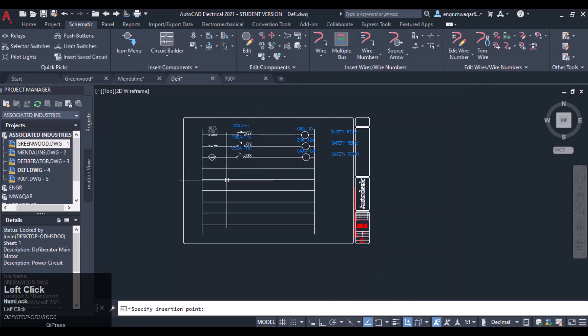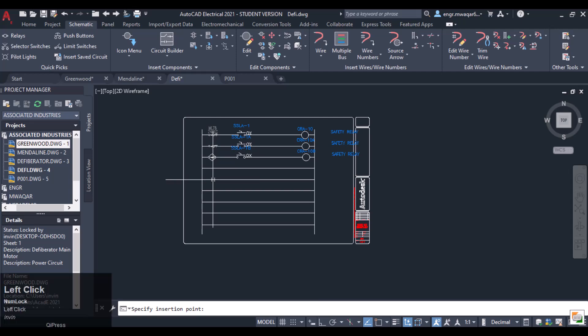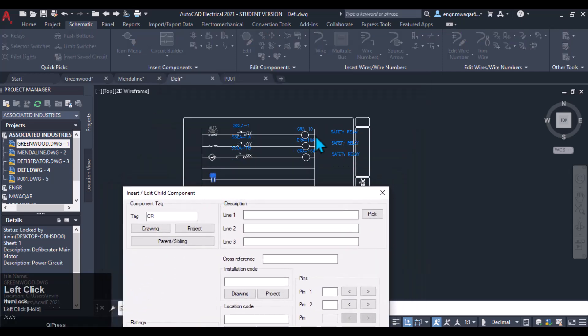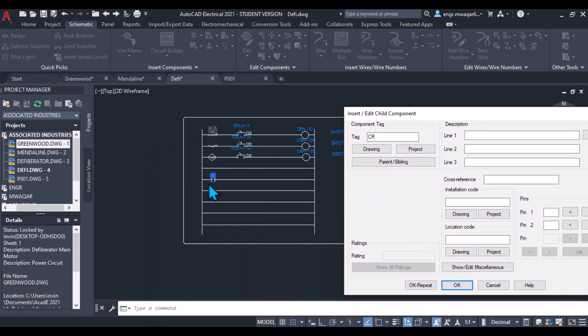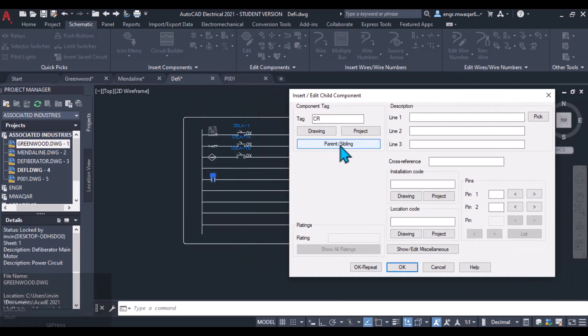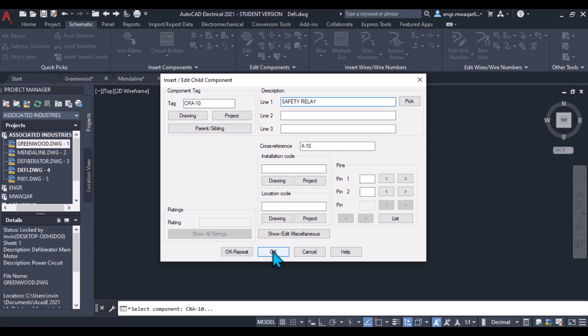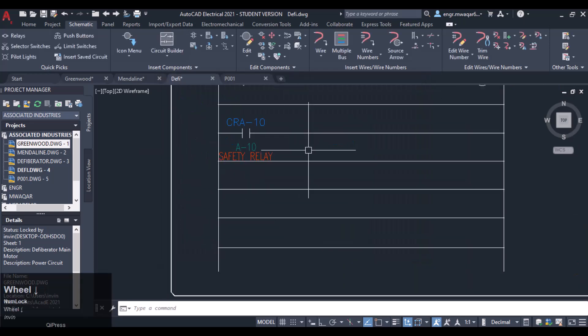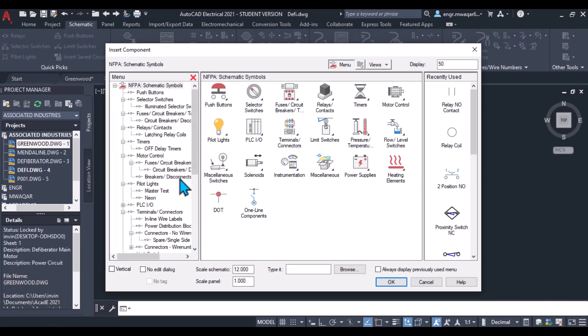When the relay operates, the normally open contact of the relay will activate. Here we will start working on parent and child symbols — the relay coil is connected to its contact. We select the parent or sibling, click on the first relay, and you can see its attributes are automatically updated — safety relay CRA-10. The relay coil is the parent component while the contact is the child component.